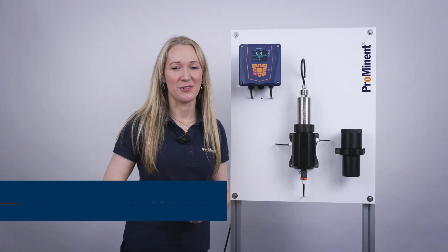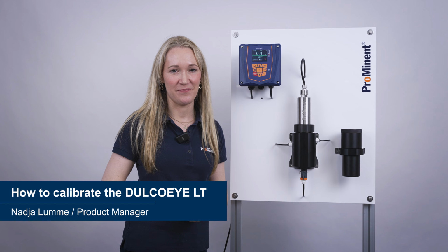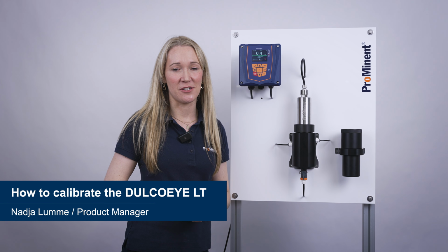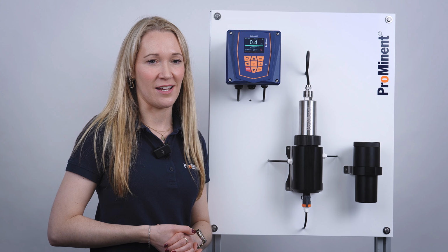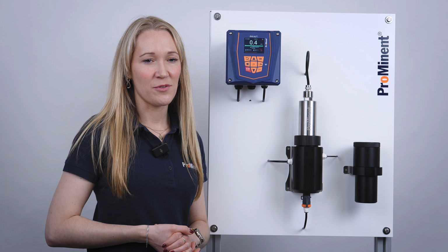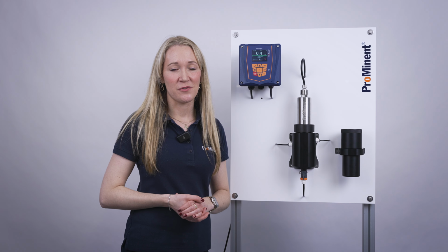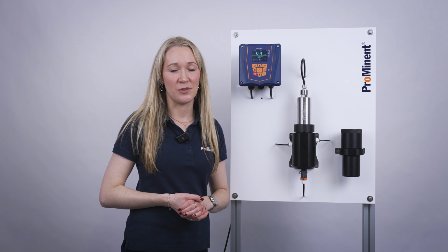In this video, I will show you how to calibrate the DULCOEYE LT. In general, it comes factory calibrated, so you can directly start to measure. If you want to calibrate the sensor, you have to use formazine. It's still the worldwide known primary standard for calibration of turbidimeters.